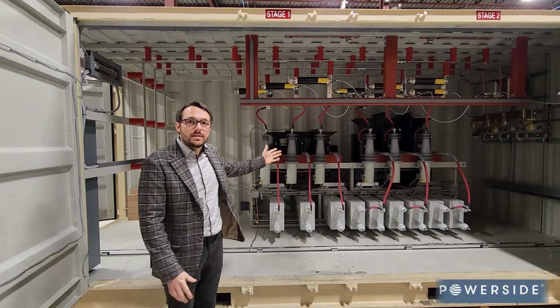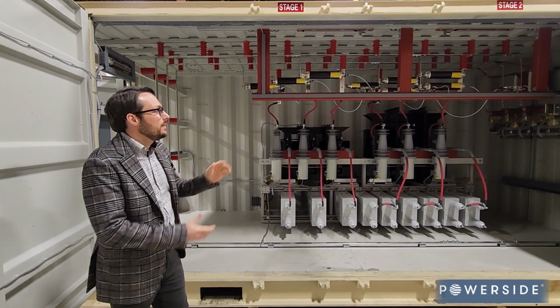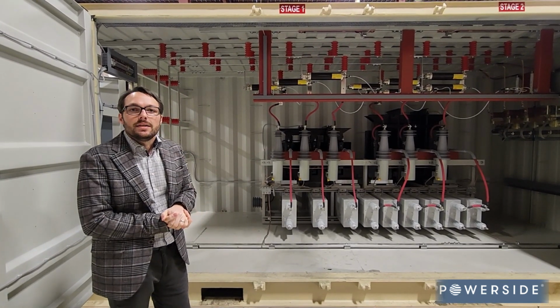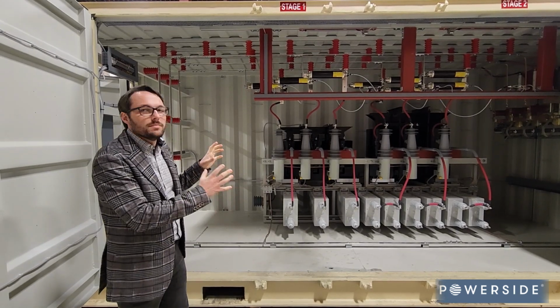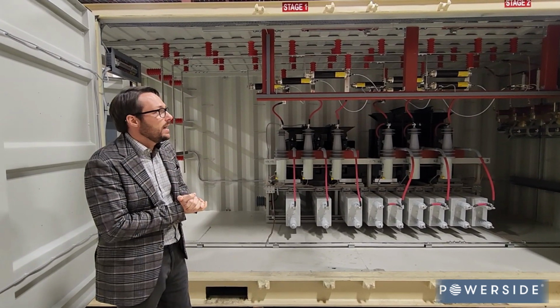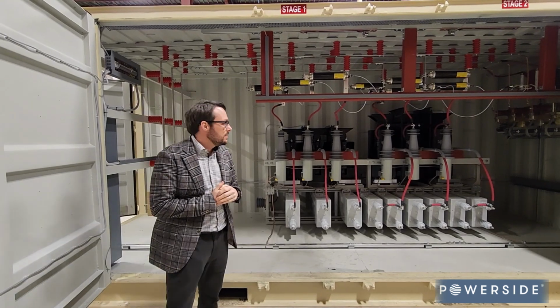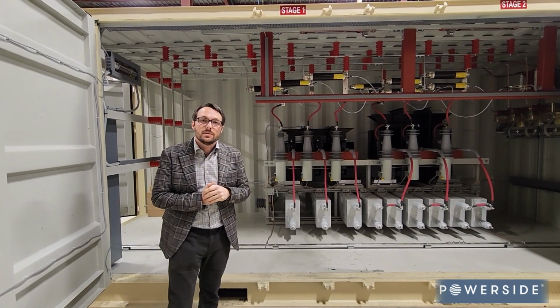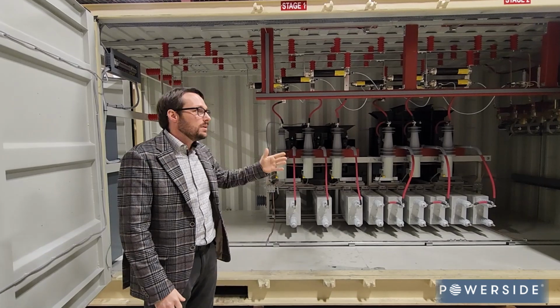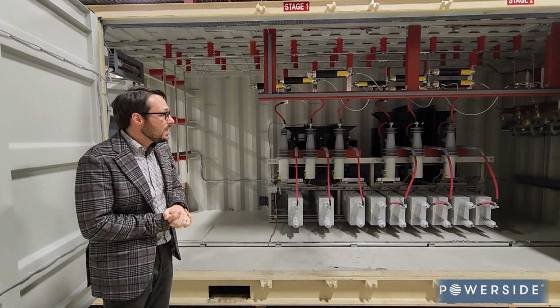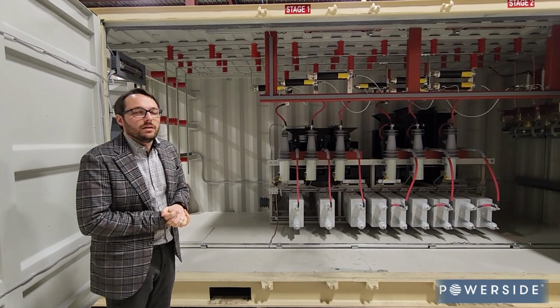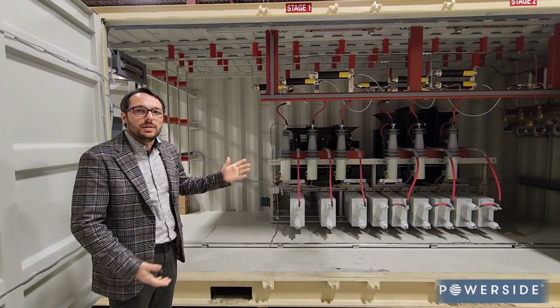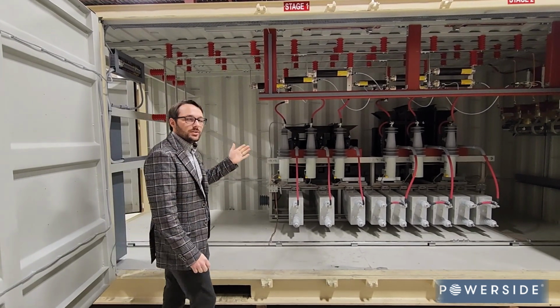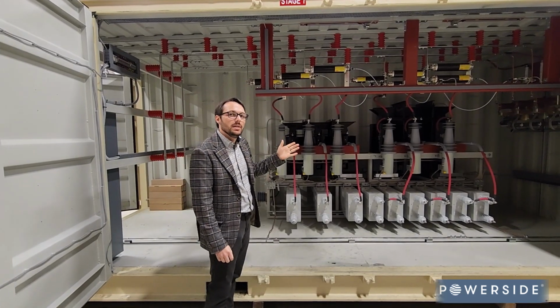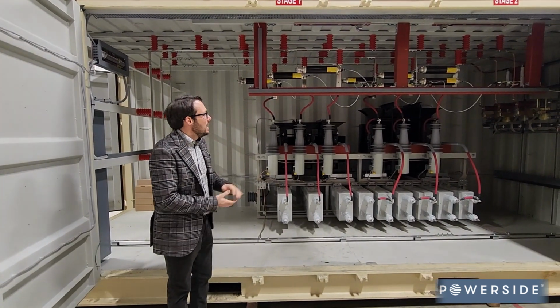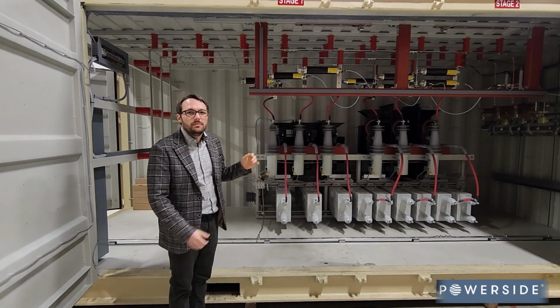What you see here is an 11 kV system that is built for a customer that needed to use our systems in a portable manner. And as you can tell here, this is a containerized solution. So this is just an average container that you can buy, and we have utilized it in a way to design a medium voltage filter. This filter is a 2-stage medium voltage detune filter, 5MVar at 11 kV.